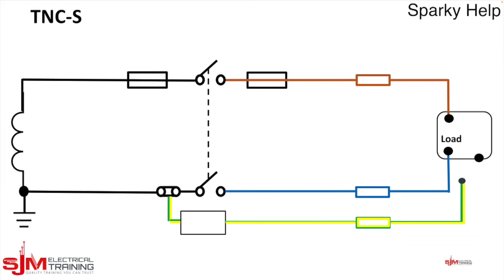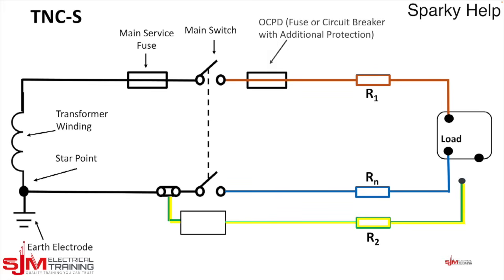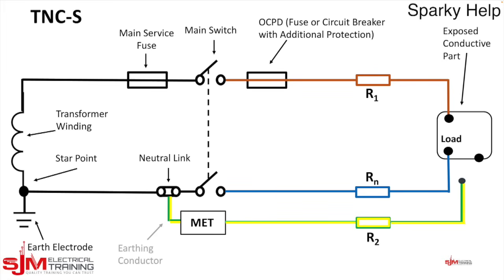And this is the important part. The cable that we run out, so whether it be an armoured or otherwise, you take the earth with you, but you do not connect it. And we label everything up as we always do, which you can see here. So we've got the earthing conductor, and what we now need is a separate earth. So we create a TT installation at your point of load. So we're going to put an earth electrode in to provide your own equipotential zone effectively, so your voltage will be common to you at that point, and therefore you have got no other stray voltages that could come in from another earth.